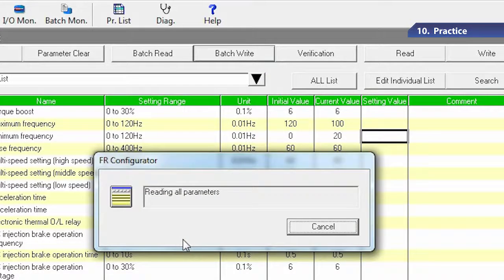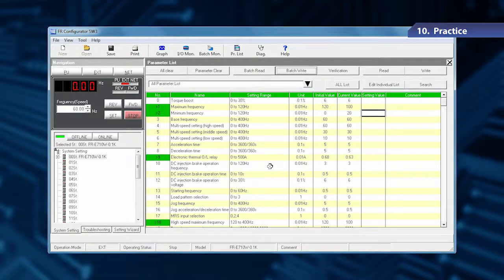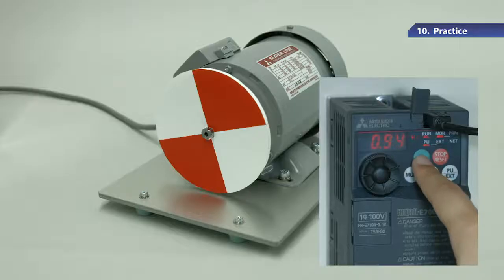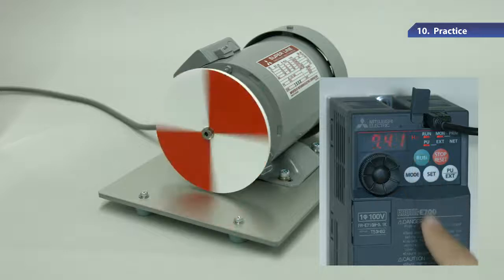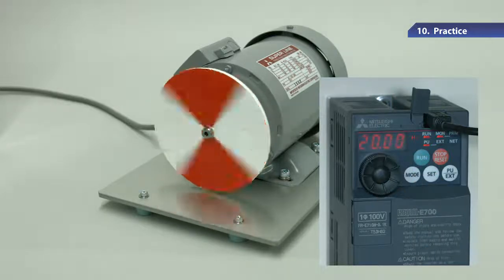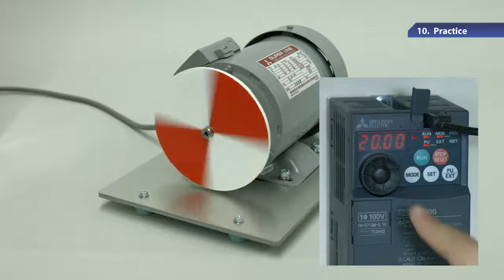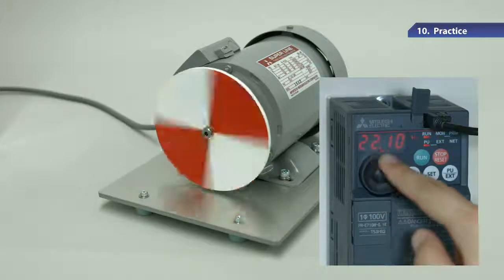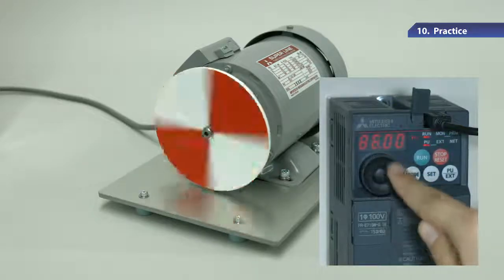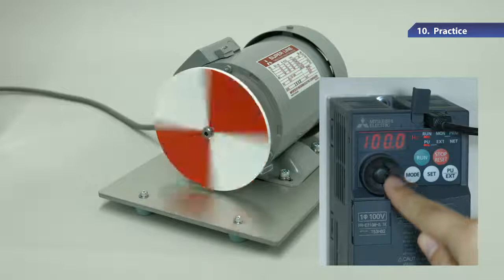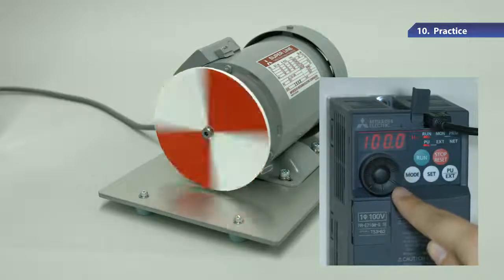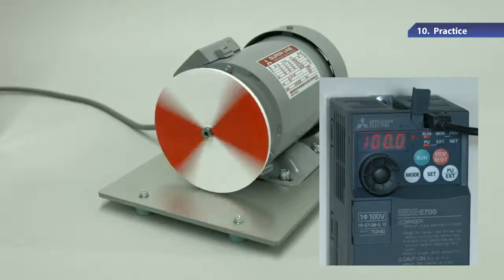Let's test with these settings. The motor starts rotating at the speed set in the lower limit frequency. Turn the M dial to increase the frequency. The frequency does not exceed 100 Hz, which is the upper limit frequency.